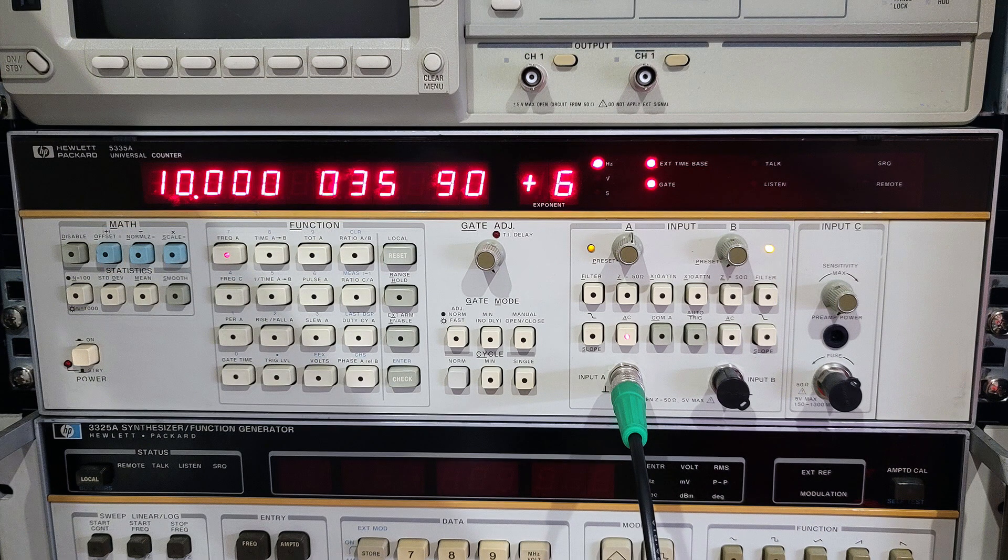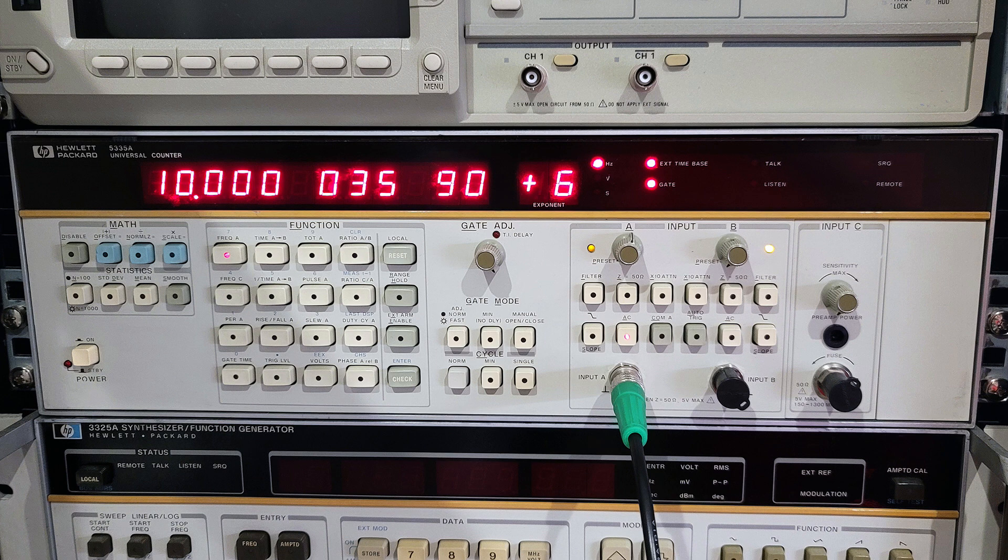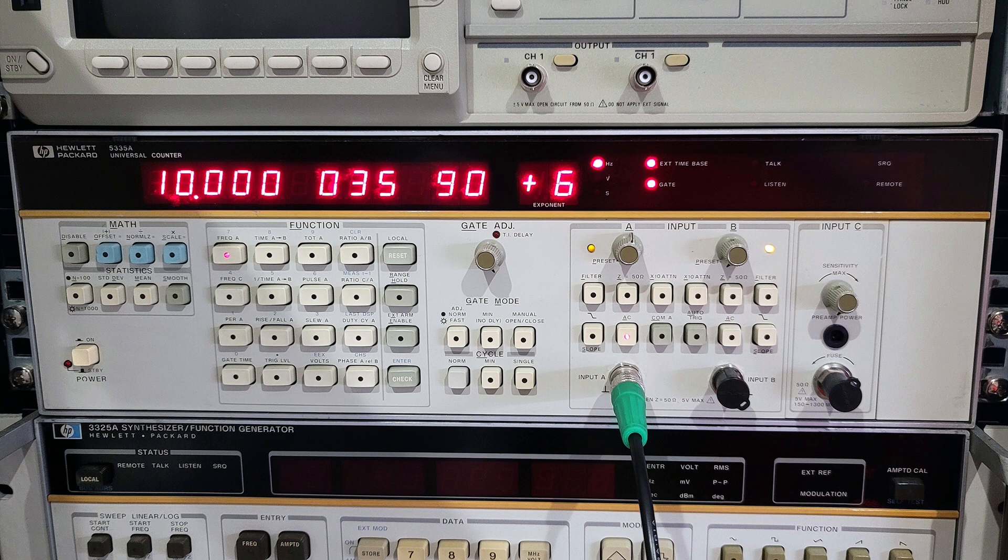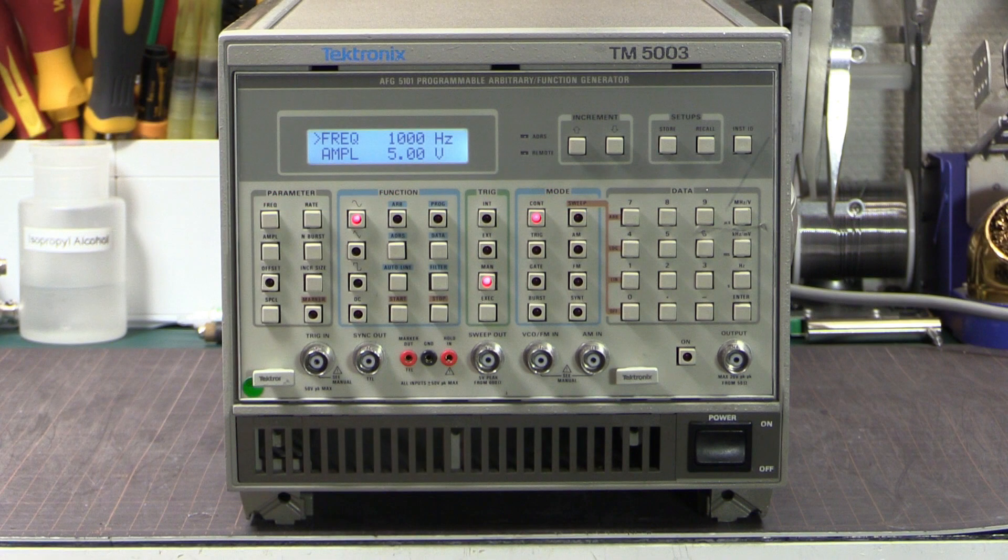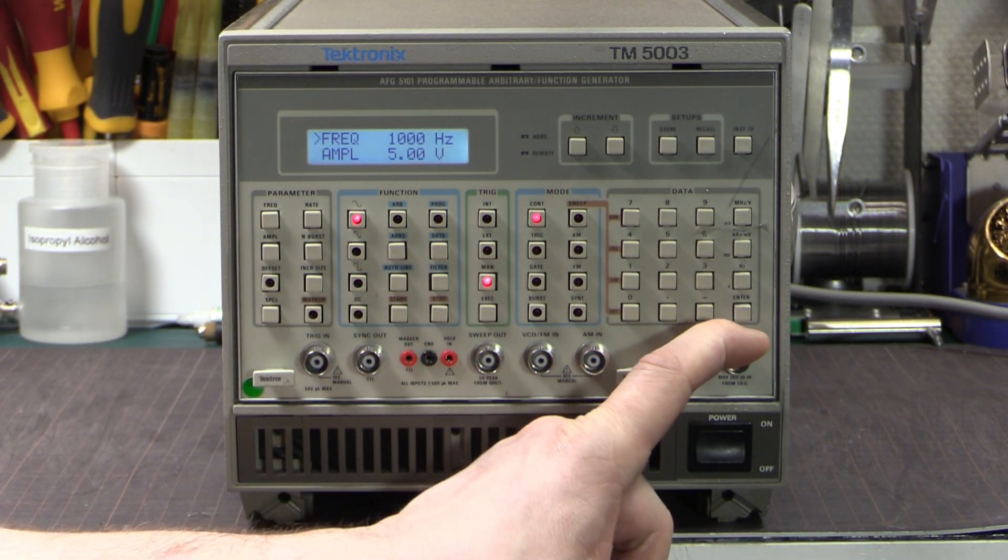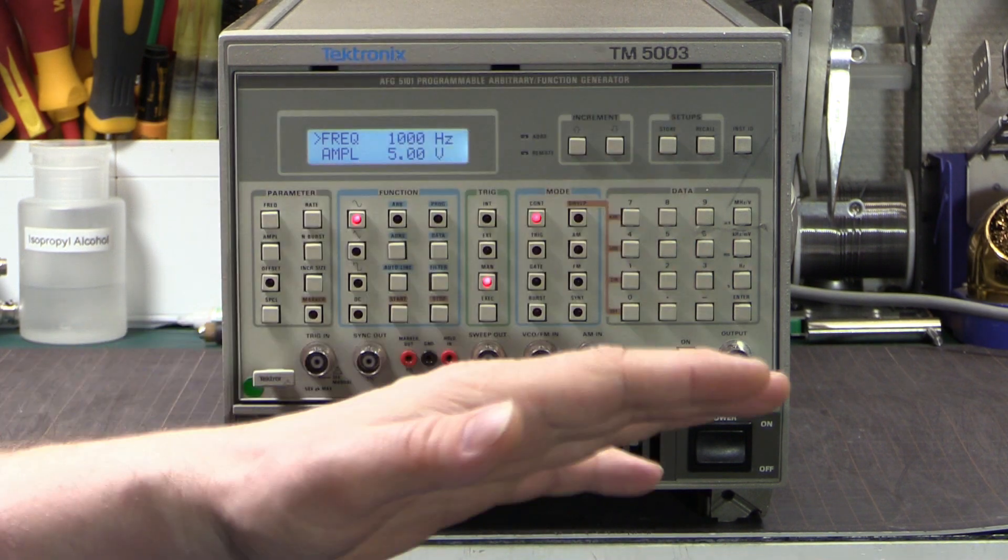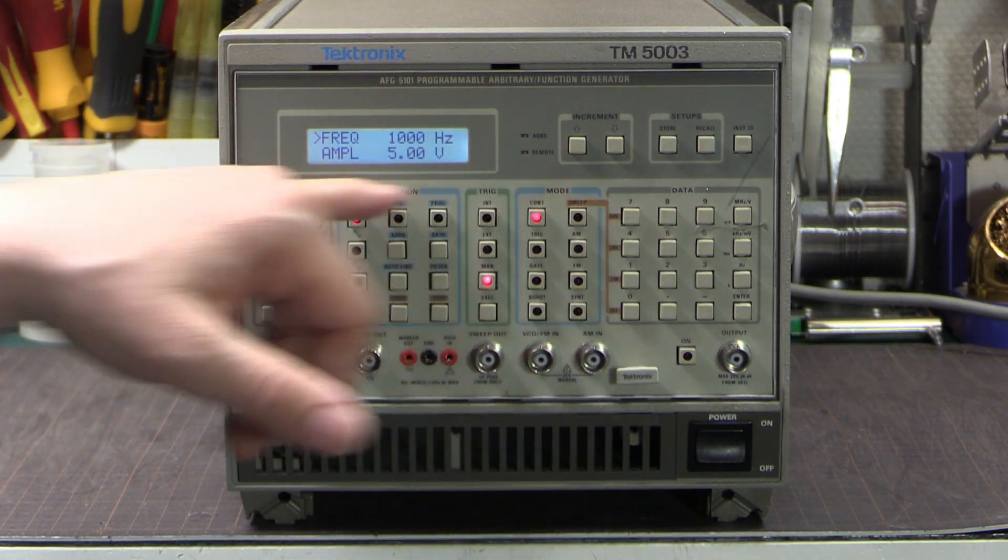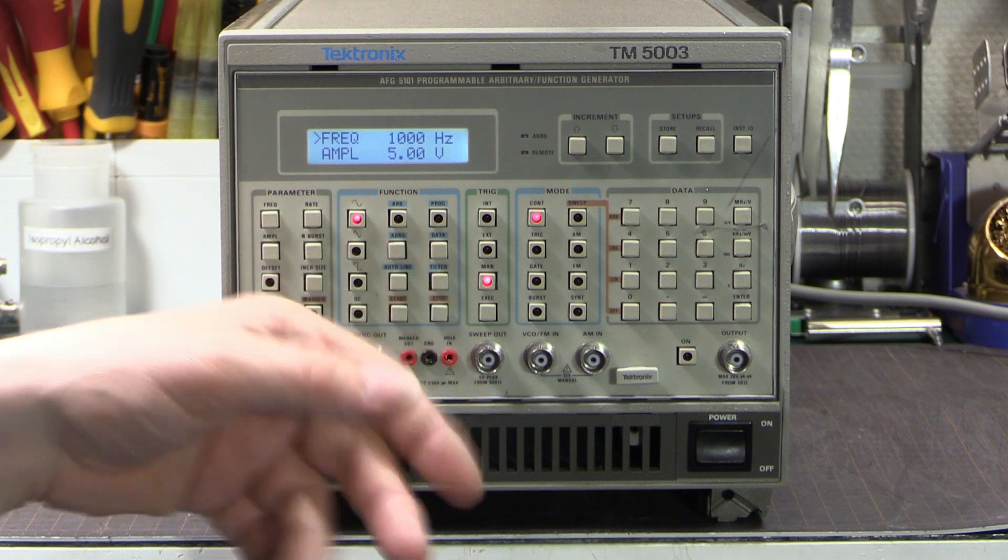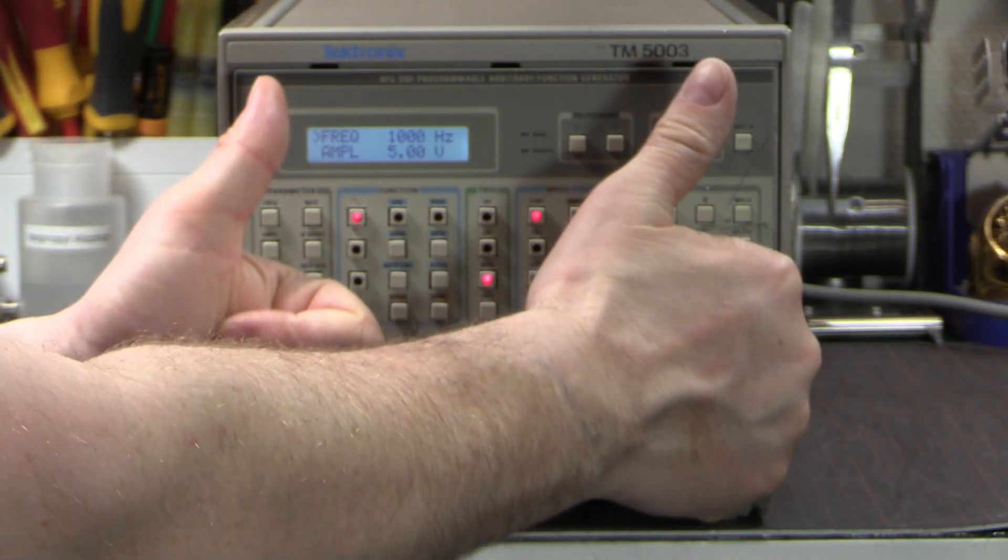If we go over to the reading with option 02 installed, look at that. 10.00003590. That's nice, that's much much better. Now the 50 ppm reading, the 50 ppm limit on the high side is 10.0005 and we are 10.000035 so we're once again an order of magnitude better. So that's again fantastic. That option 02 is obviously working. It's giving us much better output and I am a happy camper. And that is done. That option 02 board is giving us much higher accuracy on the output which is fantastic. It's working perfectly. The top row of buttons there, we fix the LEDs in there, working great. It's been adjusted, calibrated and upgraded. Two enthusiastic thumbs up. I'm really happy with the way this turned out, all finished.